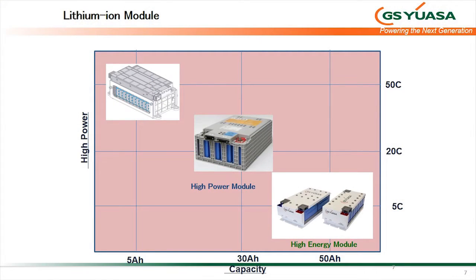Moving on to the industrial side of things and UPS, this gives some examples of the performance of modules. We've moved away from supplying cells on their own, because with a lithium-ion battery you have to integrate it with electronics to monitor the voltages and temperatures, and to balance the cell state of charge actively with resistors and switches, because it's not like lead acid, where you can balance state of charge by float charging a system. So it's a bit more complicated, and we think it's best to package all of that into a module, so we will supply the module.